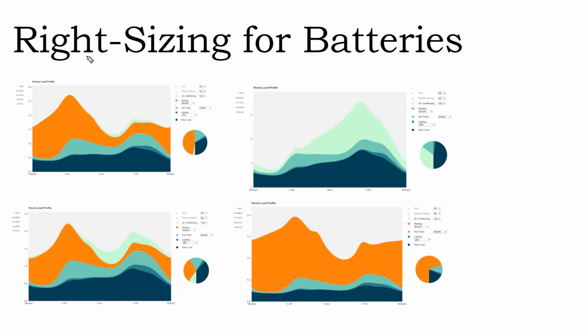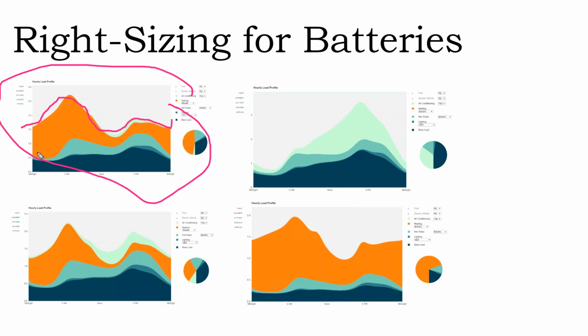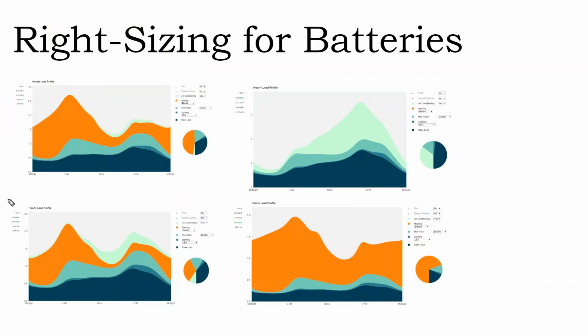The problem with these smoothed out graphs is that if you increase the resolution, you'd find your home load actually jumps way up and down. At some times your home load could be down at 500 watts, then your hot water heater and air conditioner click on and you go up above 10 kilowatts. A tankless water heater by itself can be a 20 kilowatt load, and many air conditioner units have 10 kilowatt heating elements just to defrost the unit.